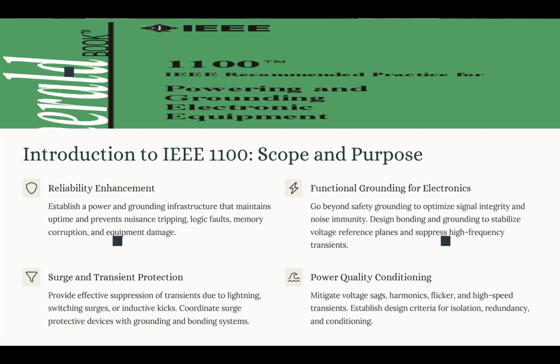Also, it recommends proper bonding so we can give the transient a low impedance path to the ground. So we basically guide the transient toward the ground system instead of letting it go through the sensitive electronic devices that we have. Another recommendation in this standard is coordination with a family of standards named IEEE C62, which covers surge protection devices. They are the detailed criteria for surge protection devices.